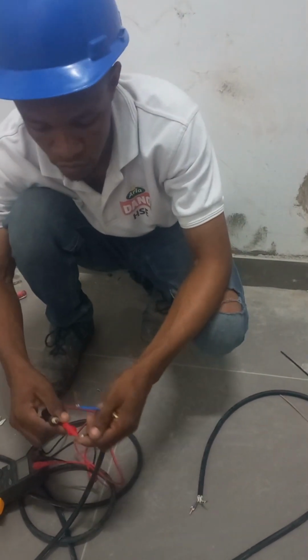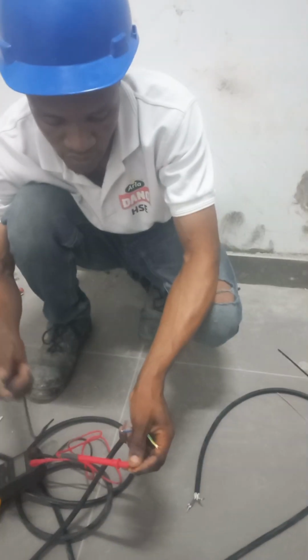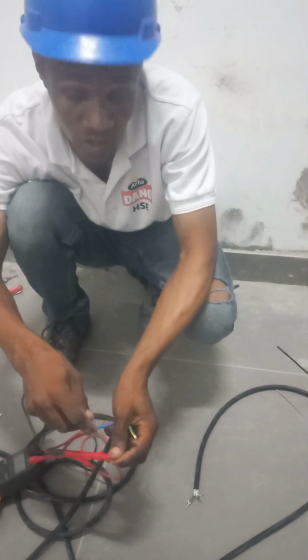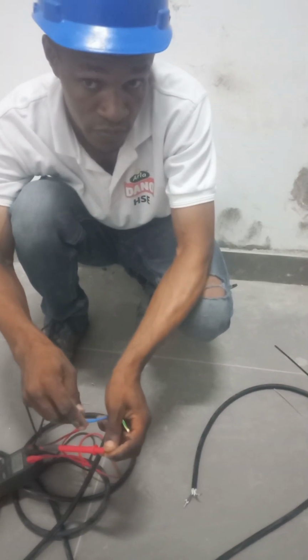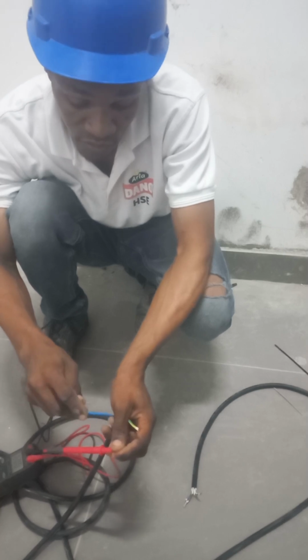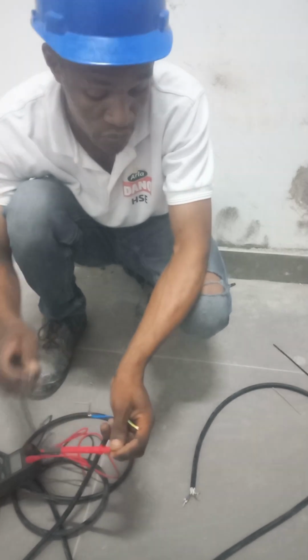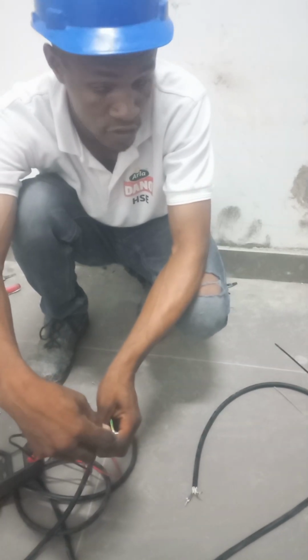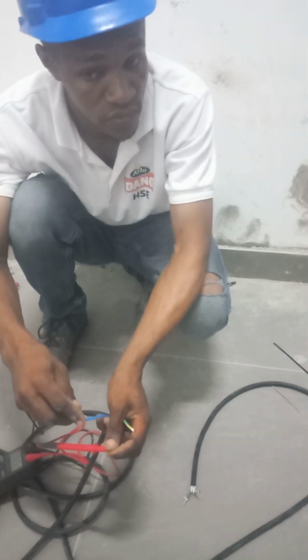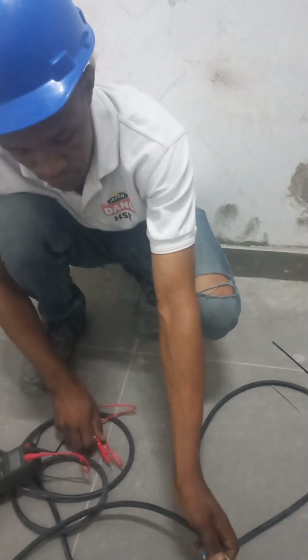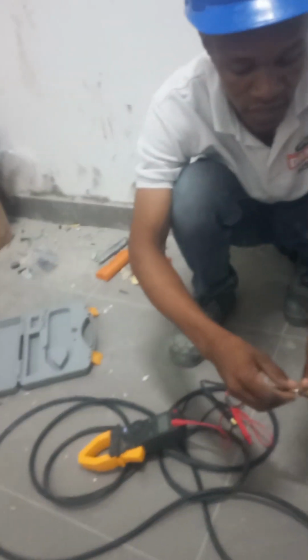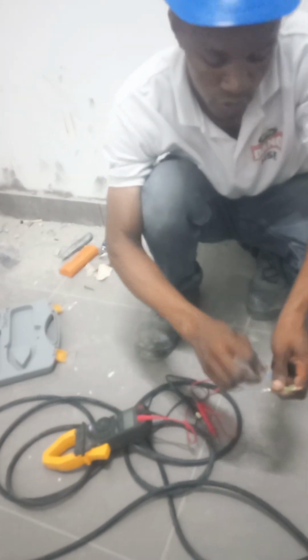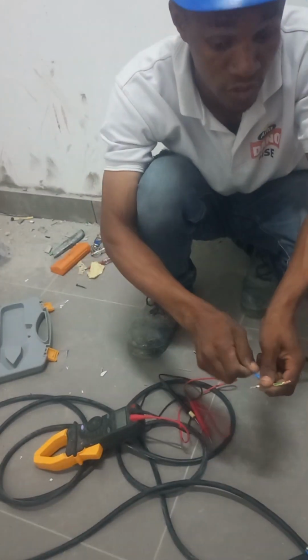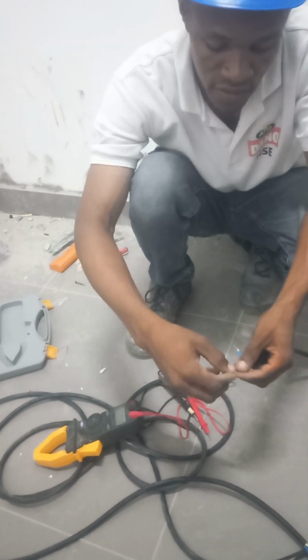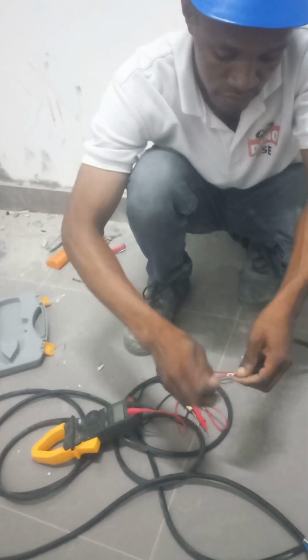Then you put one of your probes, red, any color, and put this one. You see it's making noise. If you remove it, it's not making noise. You put it at this edge, it will. You put it back, it's making noise. So now you have confirmed that this brown and blue are continuous. This continuity is okay. Now check the earth and the brown.